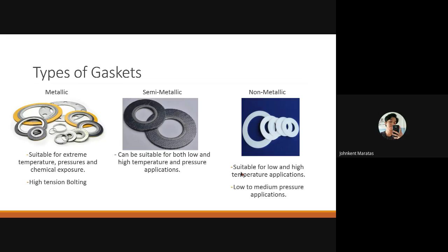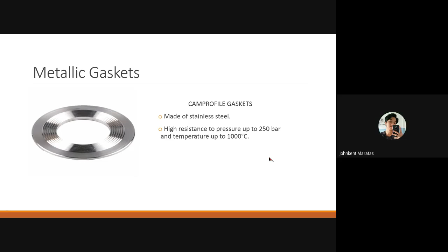So, examples of metallic gaskets. The camprofile gaskets consist of a metal core serrated on both sides, generally made from stainless steel, which will not damage flange surfaces and is easily removed. Temperature resistance is up to 1000 degrees Celsius, depending on the coating material, and they are resistant to pressures up to 250 bar.